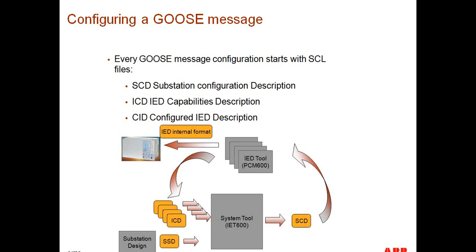And those files could be in the form of an ICD, which is an IED capabilities description. That's a file which is also referred to as a template file, which is a file that just contains the logical nodes or the data model structure of the device without any GOOSE message or report control block configuration. In the case of a CID, the CID is essentially the same thing as an ICD, a description of the data model of the relay, but on top of this, we will provide any GOOSE control blocks that are being sent, any inputs onto the relay, and any report control blocks.